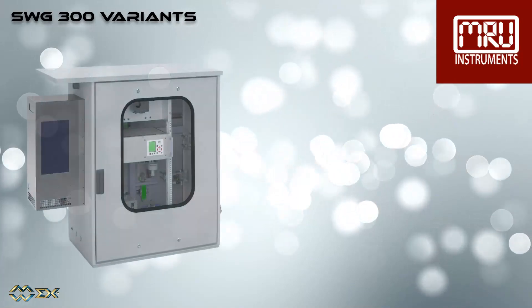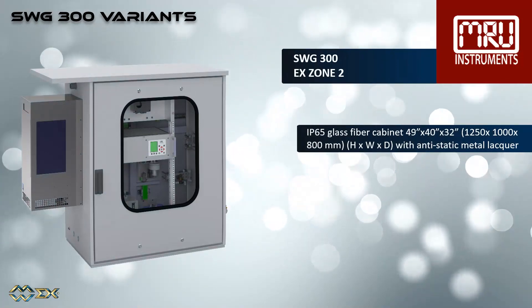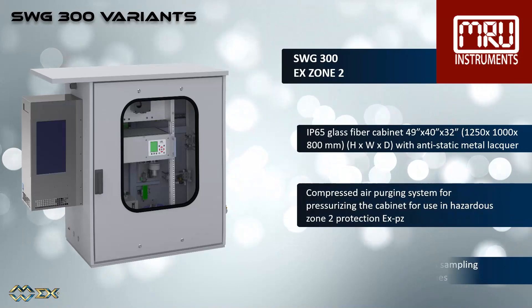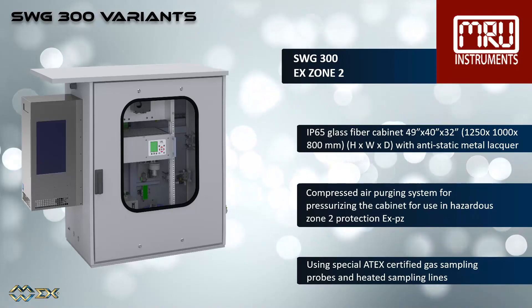The SWG 300 EX Zone 2 has an IP65 glass fiber cabinet with anti-static metal lacquer, and uses a compressed air purging system for pressurizing the cabinet for use in hazardous zone 2, and uses special ATEX certified gas sampling probes and heated sampling lines.